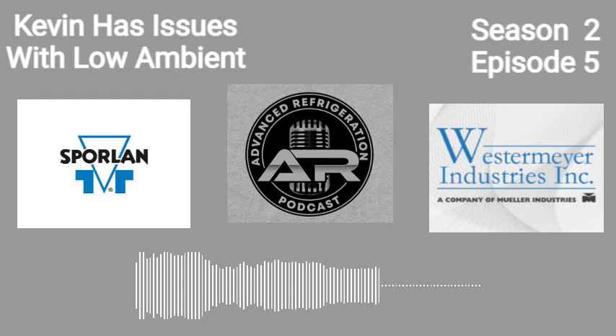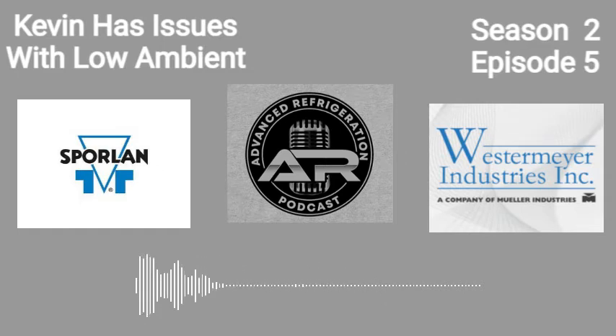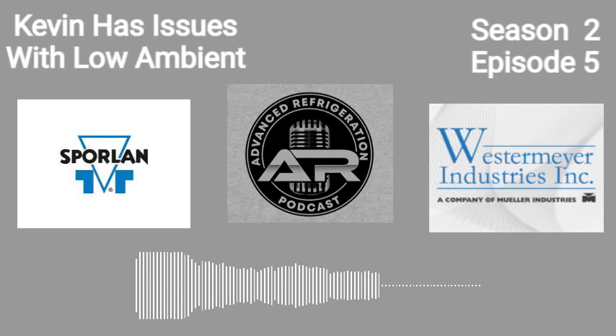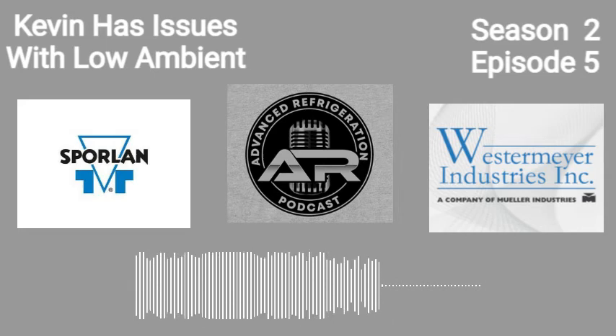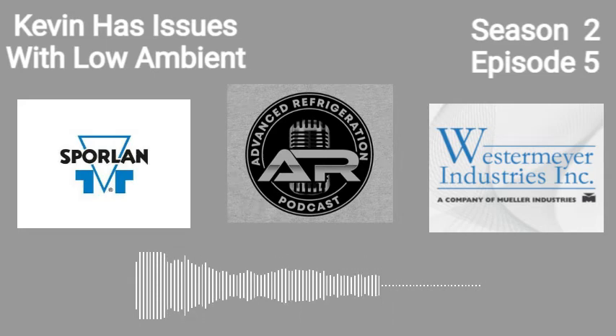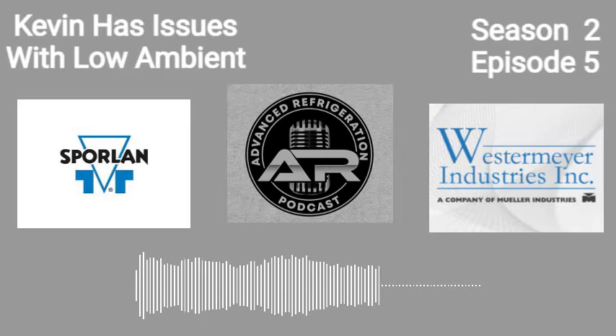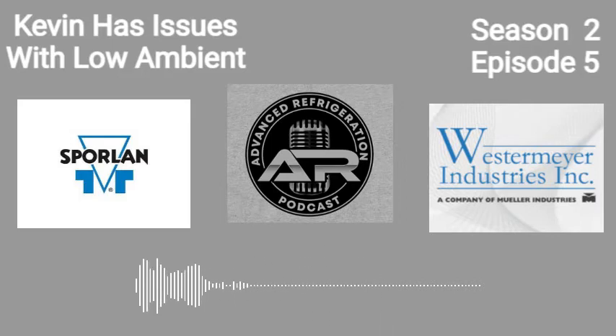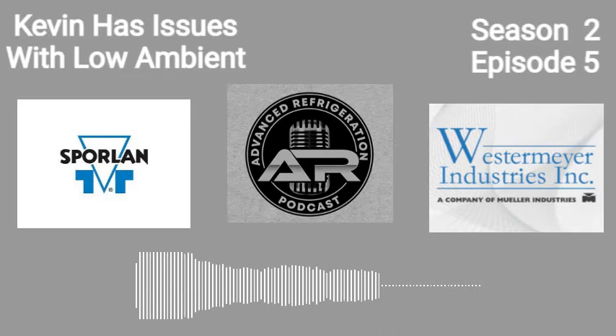What kind of TD are you running on the evaporators that you're pulling down? They're like a high TD case. I think it's like a 28 degree evap, and it's a 32 degree discharge air spec. Okay, so what saturated temperature are you running then? Like 8 degrees, 4 degrees. So you're running like a 30 degree TD. The one today was running 4 degrees. Wait, 4 degree what? Oh, 4 degree discharge air? No, evaporator.